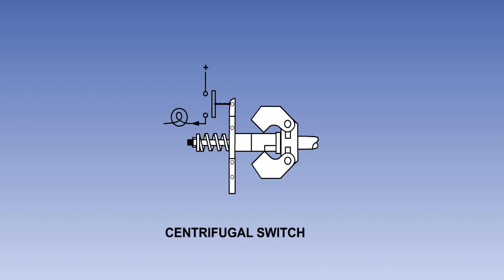Centrifugal switches can be set to activate or deactivate a circuit as the rotational speed of a device increases or decreases. In the simplified diagram shown here, the flyweights are being driven around by the component whose rotational speed is being monitored. As the speed increases, the flyweights move out, pushing the non-rotating sleeve against the spring, which in turn moves the lever arm.